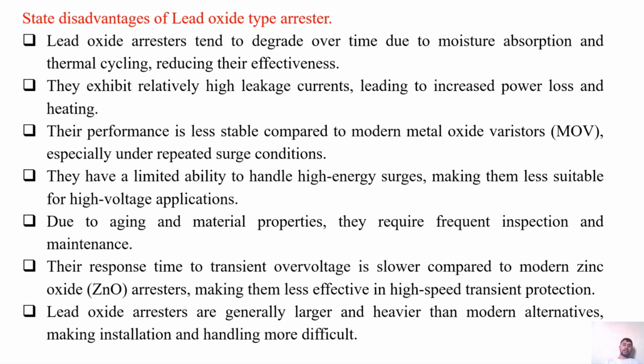They have a limited ability to handle high energy surges, making them less suitable for high voltage applications. Due to aging and material properties, they require frequent inspection and maintenance. The response time to transient overvoltage is slower compared to modern zinc oxide arrestors, making them less effective in high-speed transient protection. Lead oxide arrestors are generally larger and heavier than modern alternatives, making installation and handling more difficult. So these are several disadvantages of lead oxide type arrestor.